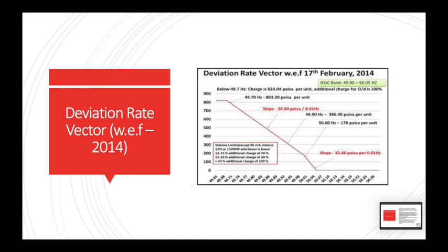For example, if my ECR rate is 3 rupees 40 paisa, then at a low frequency of 49.90 or 49.95 or less, when the DSM rate is greater than my ECR, I can continue to generate more and earn more from the grid. Though I would be supporting the grid at the moment also, the grid doesn't want to hold like this.